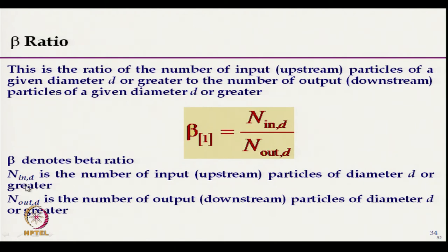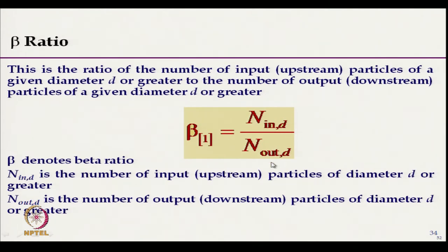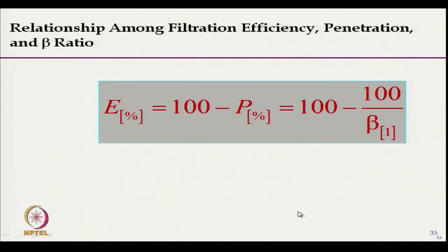N_in for diameter d is the number of upstream particles of diameter d or greater. Filtration efficiency equals 1 minus penetration efficiency. Beta ratio is the reciprocal of penetration and is not expressed as a percentage. Beta ratio is for a particular particle size and above.